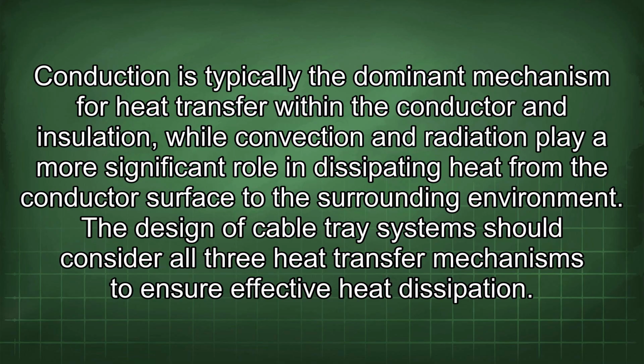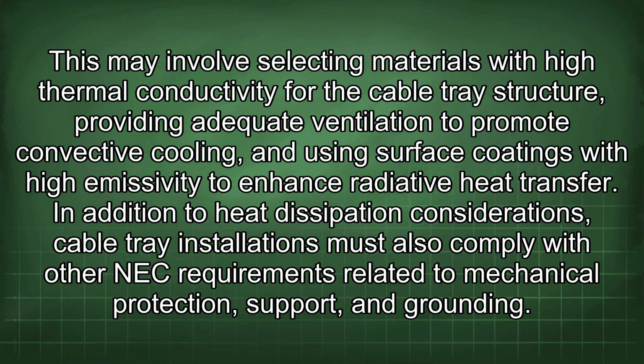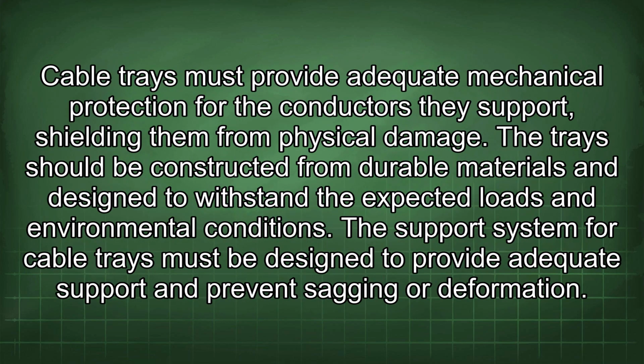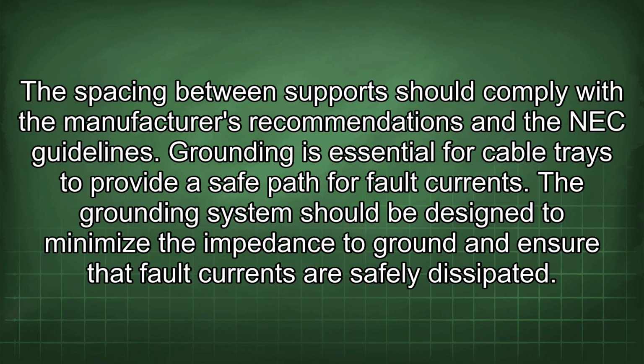The design of cable tray systems should consider all three heat transfer mechanisms to ensure effective heat dissipation. This may involve selecting materials with high thermal conductivity for the cable tray structure, providing adequate ventilation to promote convective cooling, and using surface coatings with high emissivity to enhance radiative heat transfer. In addition to heat dissipation considerations, cable tray installations must also comply with other NEC requirements related to mechanical protection, support, and grounding. Cable trays must provide adequate mechanical protection for the conductors they support, shielding them from physical damage. The trays should be constructed from durable materials and designed to withstand the expected loads and environmental conditions. The support system for cable trays must be designed to provide adequate support and prevent sagging or deformation. The spacing between supports should comply with the manufacturer's recommendations and the NEC guidelines.